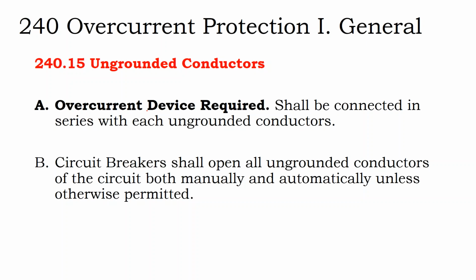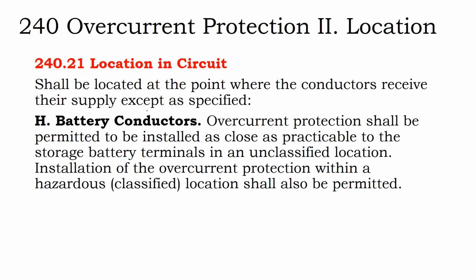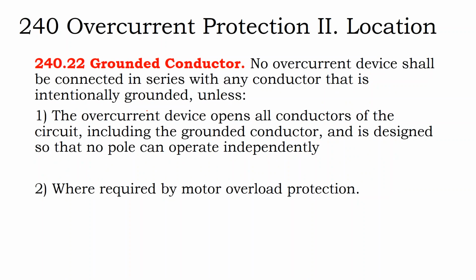Ungrounded conductors have overcurrent protection devices as well to prevent overcurrent situations. Battery conductors, overcurrent protection shall be permitted to be installed as close as practical to the storage battery terminals in an unclassified location. So often your battery overcurrent protection devices are just the DC breakers in the service panel the batteries are landing on. No overcurrent device shall be connected in series with any grounded conductor unless it opens all the conductors of the service, including the grounded conductor, so that no pole can operate independently.